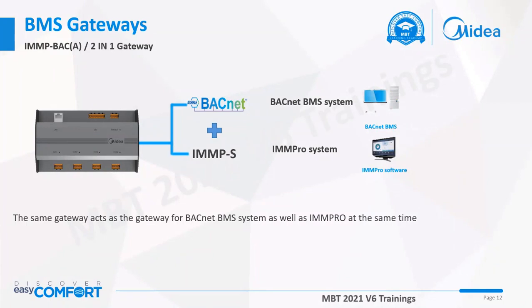Okay, so IMMP-BAC(A), we call it a two-in-one gateway. Why do we call it a two-in-one gateway and what are the advantages? As I mentioned, this can connect to the BACnet BMS system, but we also have our IMM Pro system. So this acts as a two-in-one gateway for both of these. How does it work? Suppose you have a system, you connect the outdoor unit XY of that system to this BACnet gateway and you can connect it with one computer, and in this computer you install the IMM Pro software and you install the BACnet BMS software also. Both the softwares will work parallelly. You don't need two gateways for that. So that is why we call it a two-in-one gateway.